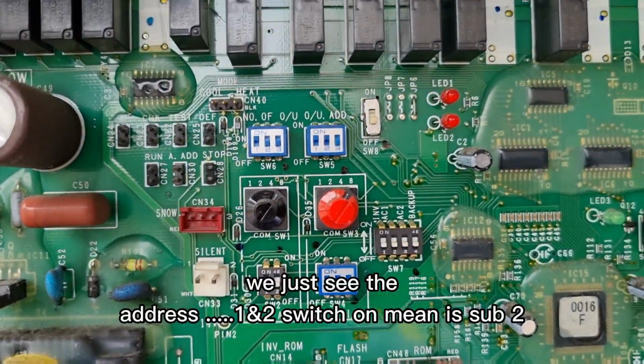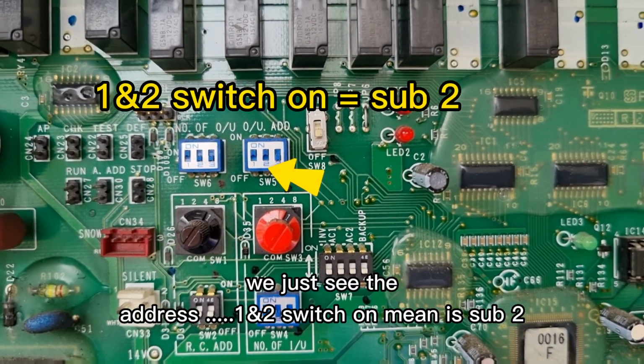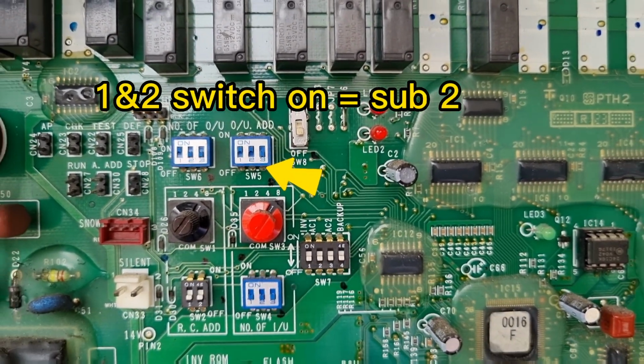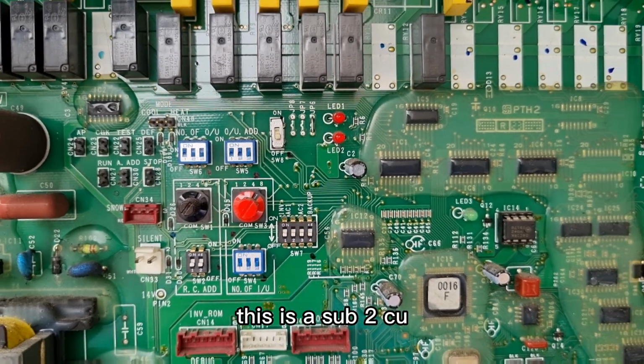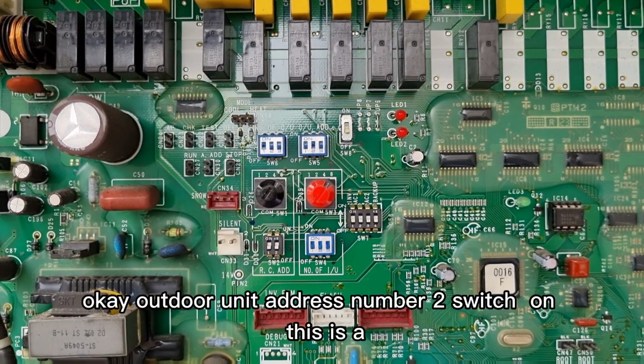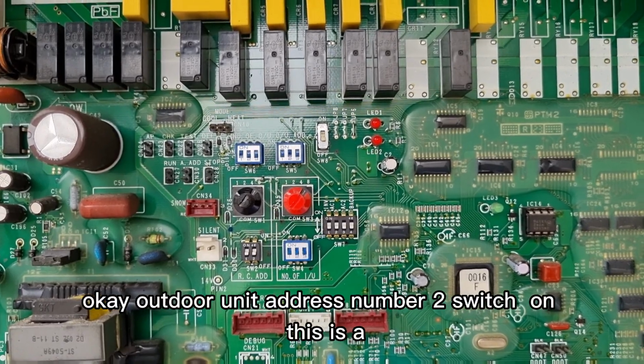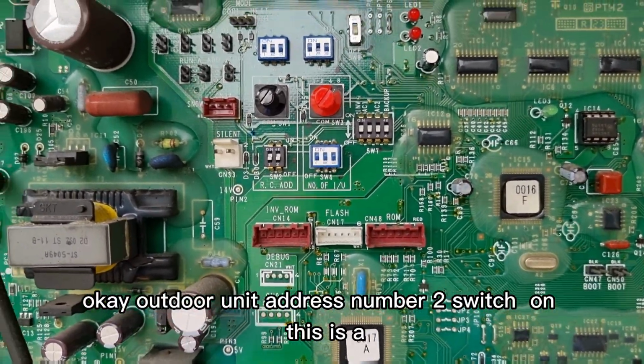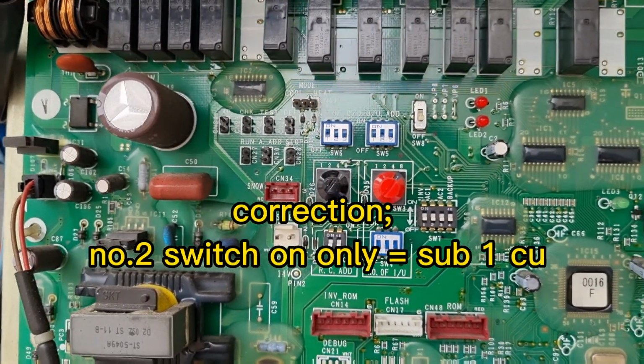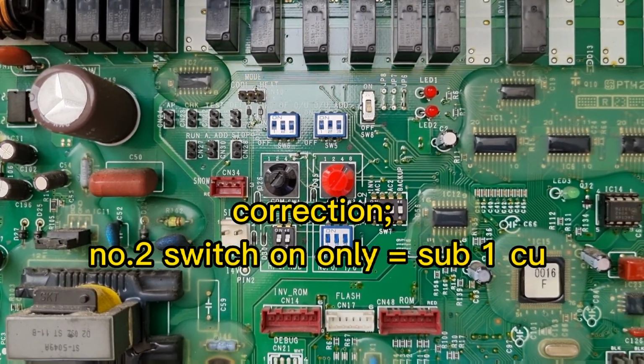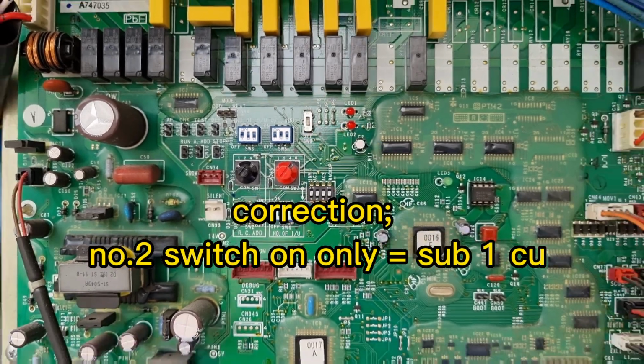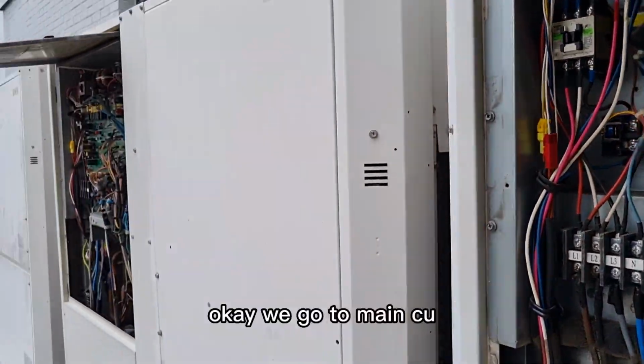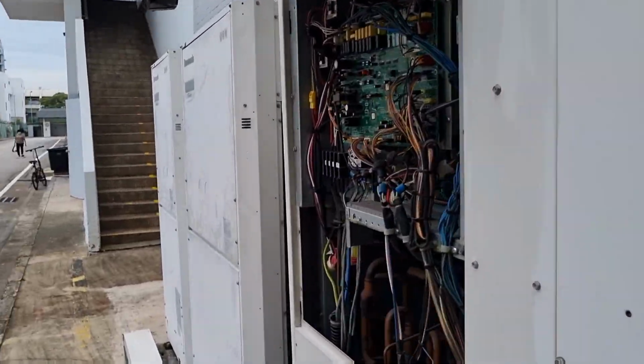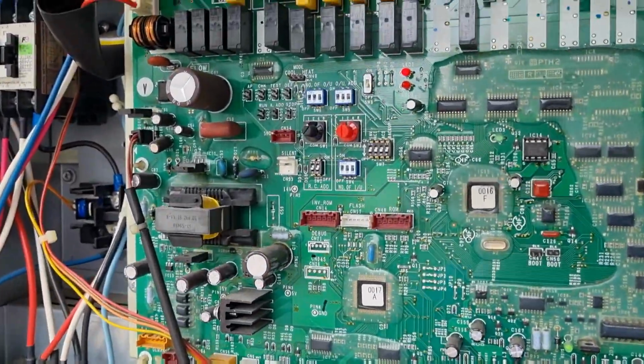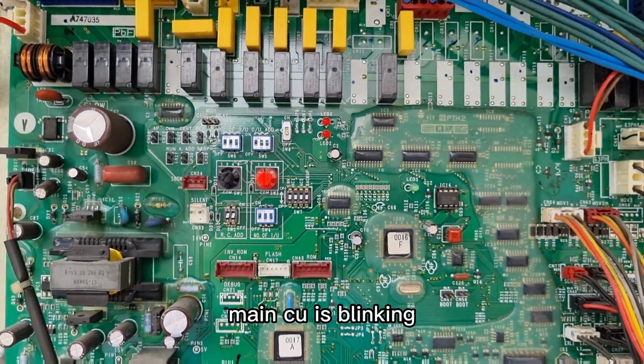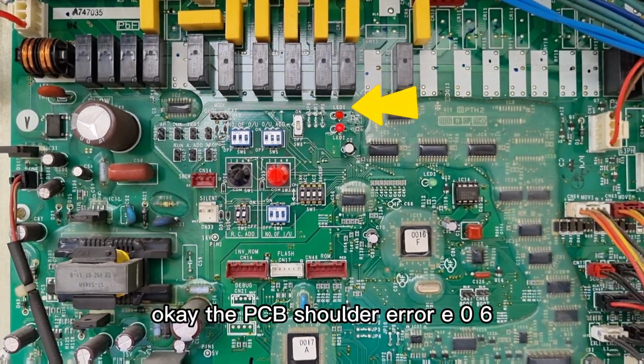Okay, for the subunit, we just see the outdoor unit address, numbers 1 and 2. This is a sub 2 CU. Okay, outdoor unit address, number 2. This is a sub 1 CU. Okay, we go to the main CU. Okay, the main CU is blinking. The PCB shows the error E06.